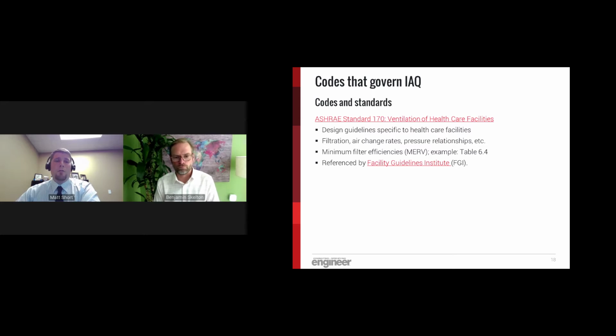Moving on, for healthcare facilities, ASHRAE Standard 170 provides design ventilation standards for specific healthcare spaces. This standard will include filtration requirements, air change rates, pressure relationships very similar to 62.1, but it'll focus primarily on healthcare. In regards to the filtration requirements, Table 6.4 provides a standard for filter MERV ratings for equipment serving various healthcare spaces. And it's important to mention that ASHRAE Standard 170 is referenced by the Facility Guideline Institute, or FGI, which we'll discuss further on the next slide.